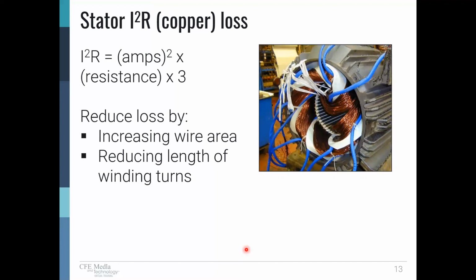The stator losses are what we call the I squared R, that current squared times resistance. We see a formula up here, the amps squared times the resistance, and that's a per-phase resistance times 3 for 3-phase, which is the majority of the motors that we see in commercial buildings and industry. As a manufacturer or as a rebuilder, we can reduce the losses in the repaired product by increasing the wire area. The manufacturer can do the same if they change the design criteria. Also, reducing the length of the winding turns. The winding coils go through that magnetic core, and the variable is where the windings come out of the core and go around and come back in. All of this area is not active. It's not inside a magnetic material. So we want to keep that to a minimum.